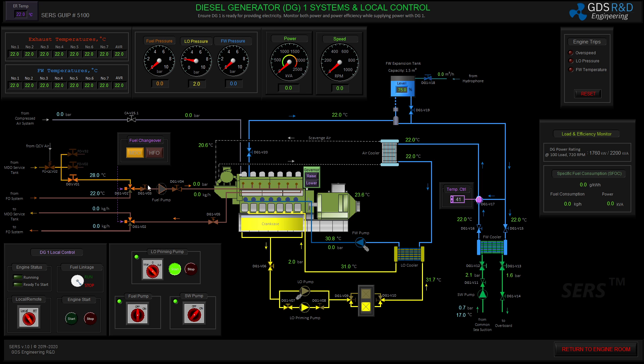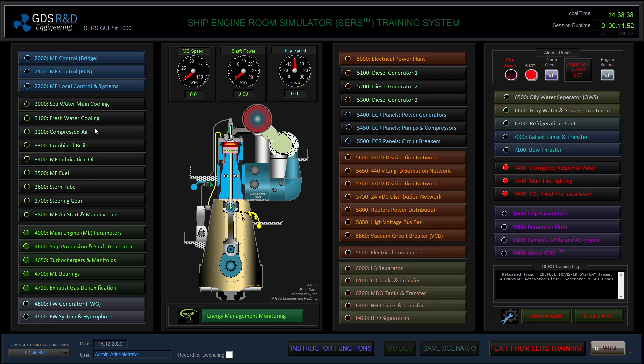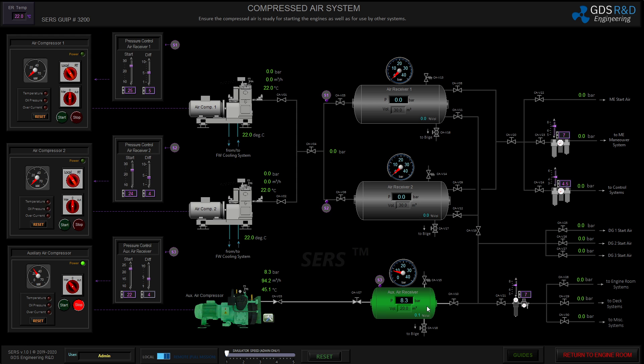I'm going to open the outlet valve of my diesel service tank so I can supply fuel to my fuel pump and then to the generator. I will start the fuel pump. The fuel pump is supposed to supply a fuel pressure of around eight to eight and a half bar, and it is very stable right now.